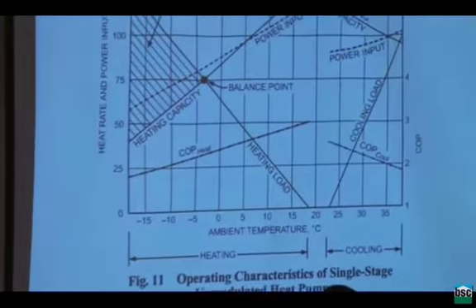It still works in Houston because they don't spend that many hours below 47 degrees. It doesn't work so good in Boise, Idaho. And so when it gets really cold, 47 degrees doesn't make much sense. But the rating point is 100%. What will typically matter is going to be closer to what they're showing here, rated at about 10 degrees, a little less, between 5 and 10 degrees Celsius.